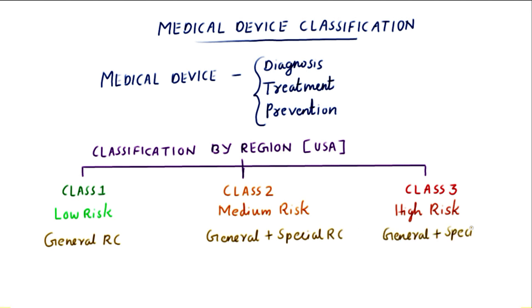Class 1 devices require general regulatory control, Class 2 devices require general plus special regulatory control, and Class 3 devices require general plus special regulatory control as well as pre-market approval. Special regulatory control requires special labeling requirements, mandatory performance standards, and post-market surveillance.